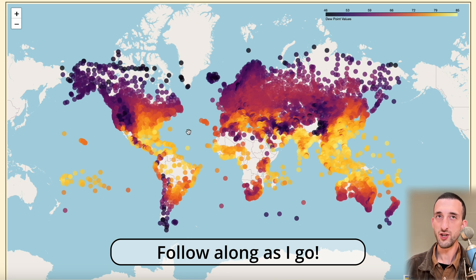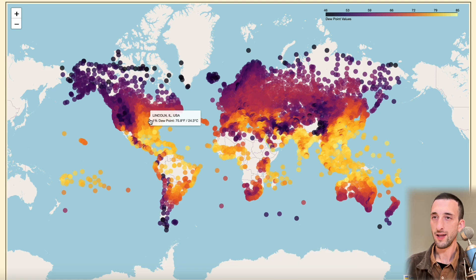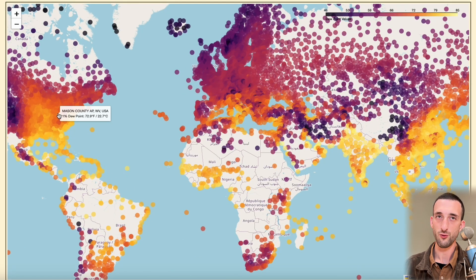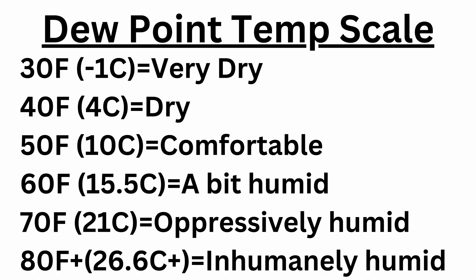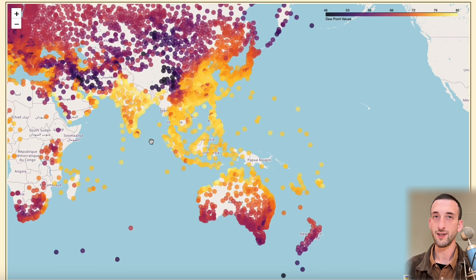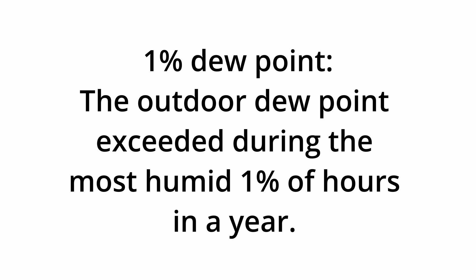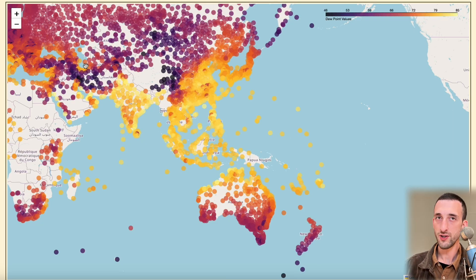Here's the first map, which shows how humid each location gets. The darker color is less humid and the lighter color is more humid. What's special about this map is that it uses dew point instead of relative humidity. Relative humidity is an incredibly misleading way to assess the amount of moisture in the air. Let's quickly review the dew point scale: 30°F is very dry, 40 is dry, 50 is comfortable, 60 is a little humid, 70 is oppressively humid, and 80+ is inhumane. Each location shows the 1% dew point — the outdoor dew point exceeded during the most humid 1% of hours in a year. It's a much more informative metric than average humidity.